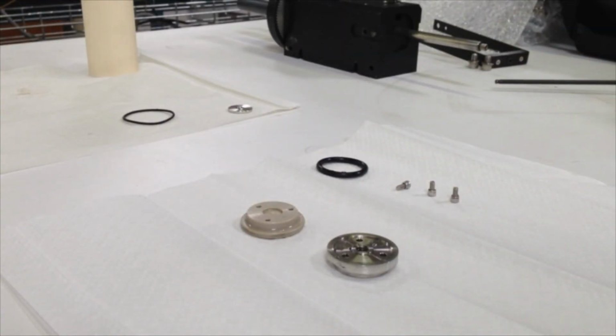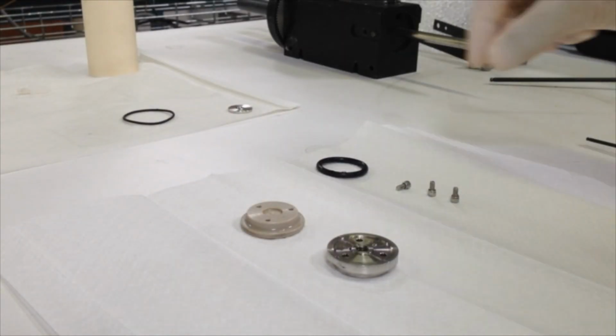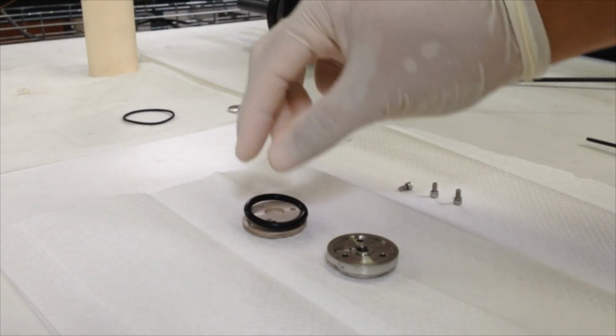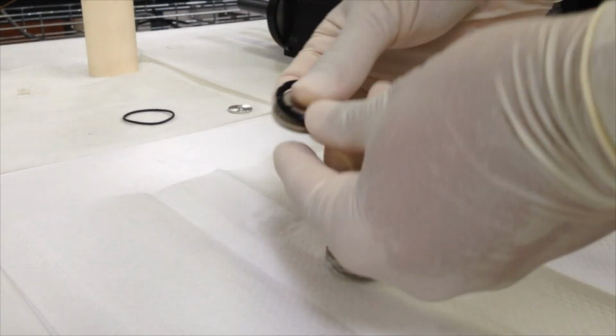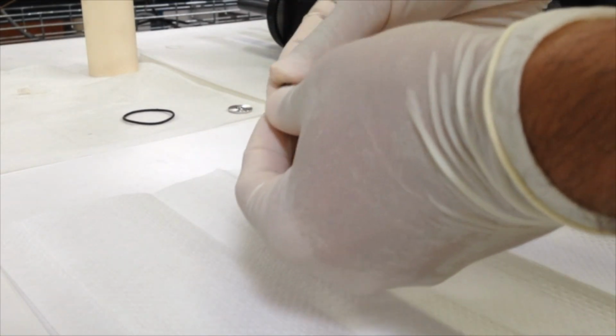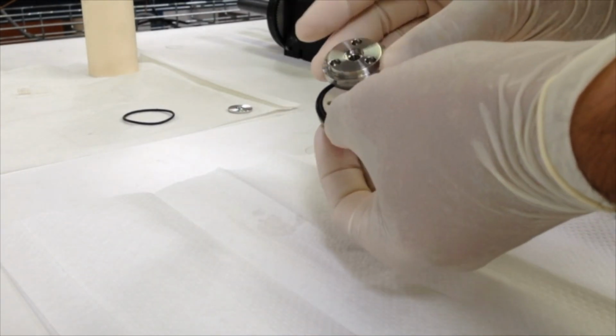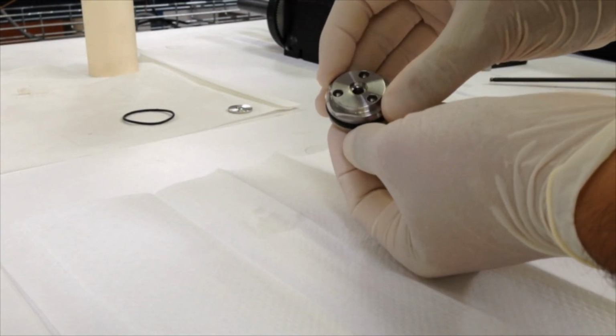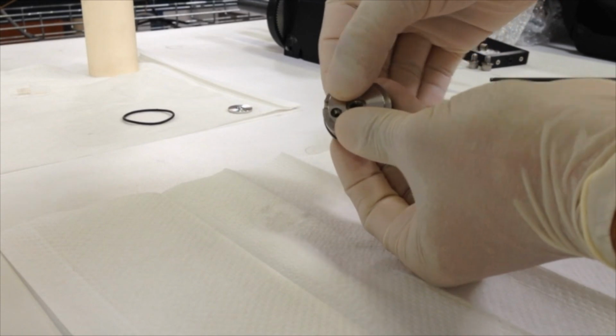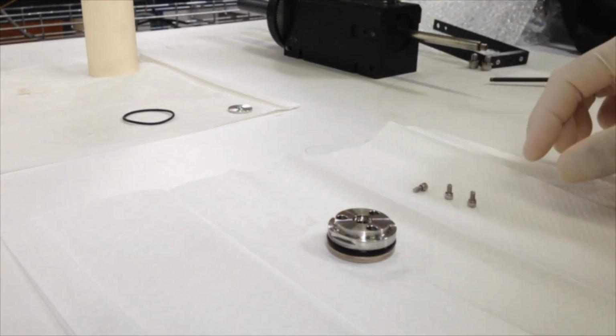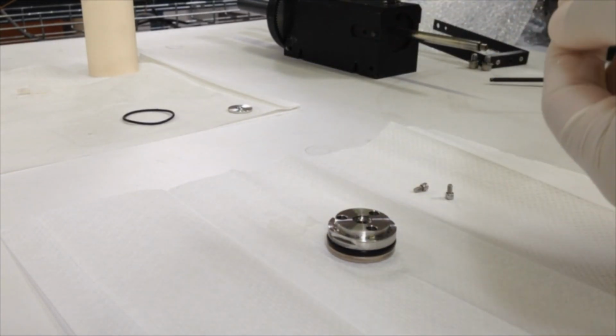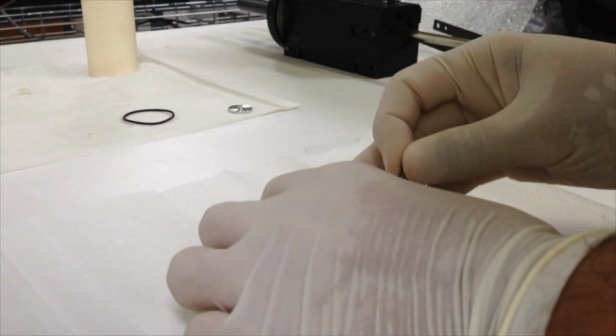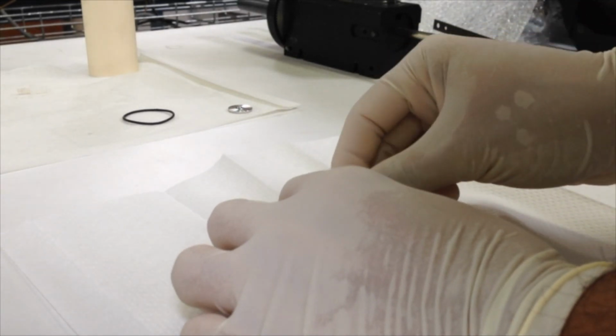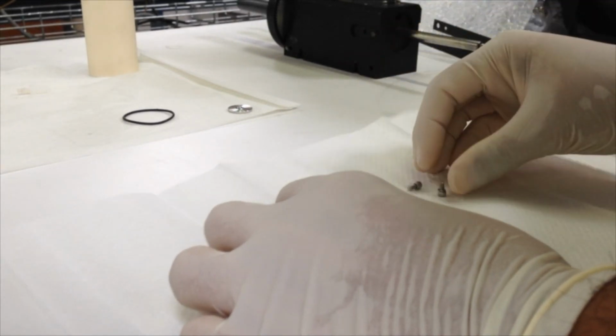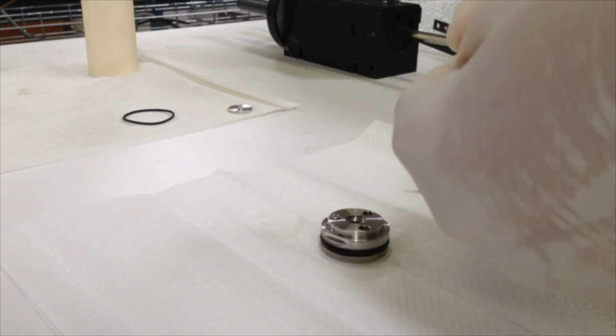Assemble the piston head by placing the cleaned O-ring onto the PEEK piston head, and then place the metal piston face on top. The PEEK piston head and the metal piston face will snap together. Line up the 3 holes and install the new screws and washers. Do not over-tighten the 3 screws. You do not want to strip out the threads of the PEEK piston head.